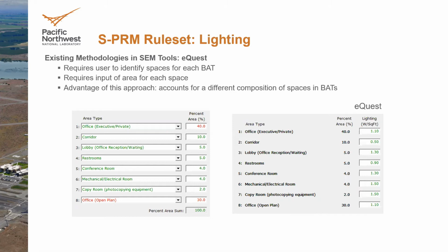We kind of go a middle ground between these two approaches, where we do the building area method, but most buildings will have 2, maybe 3 or 4 building types in them. So if it's office, we'd have a building-level office and wouldn't break the corridor out, but if you had office and library, or other building type differences, we'd break those out, and also break out labs or other space types that have a substantially different load.